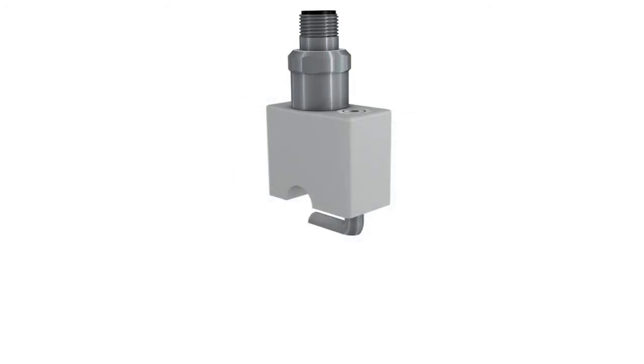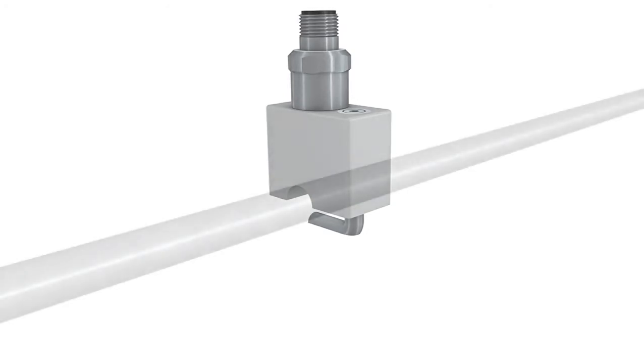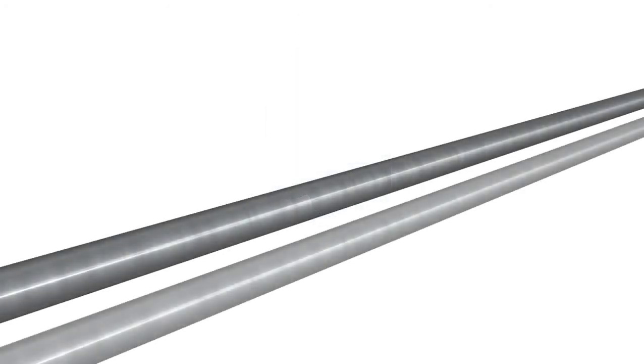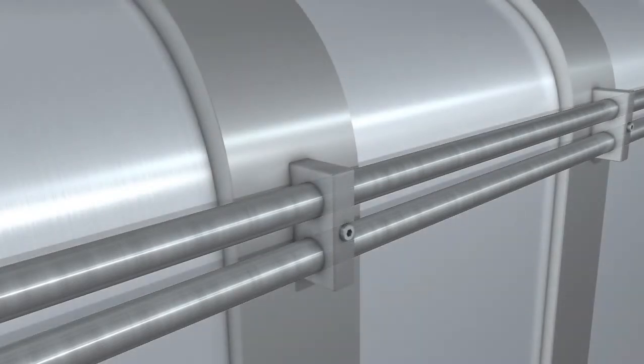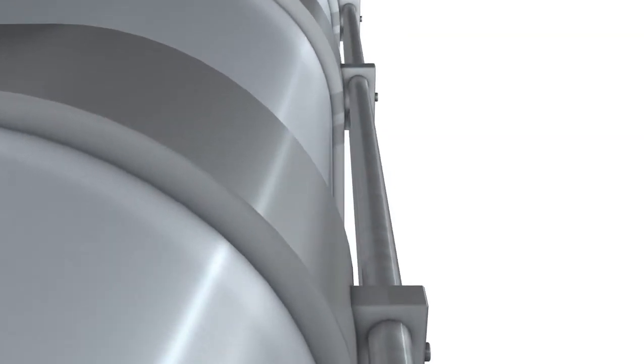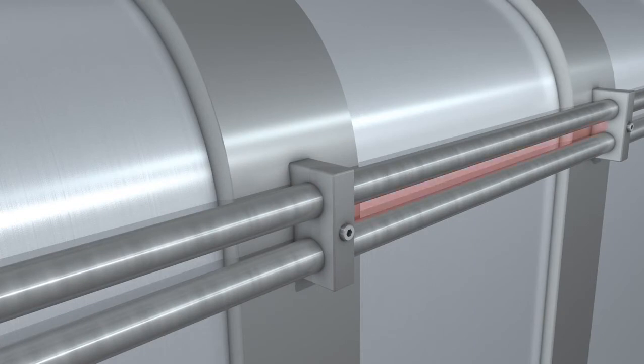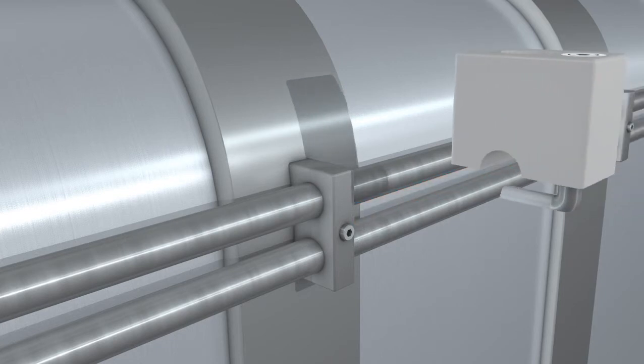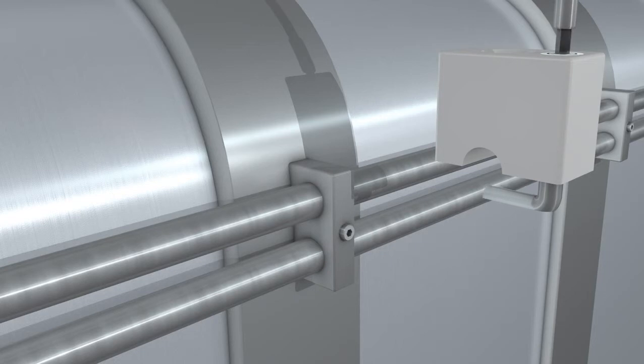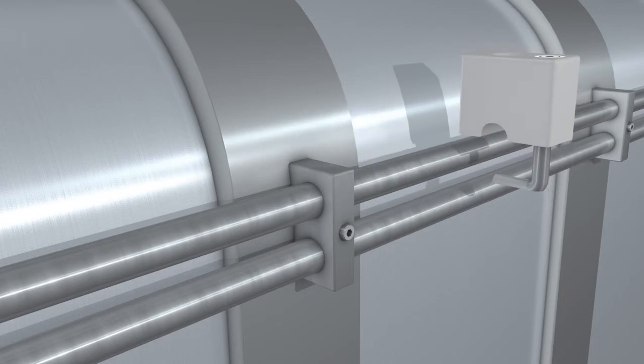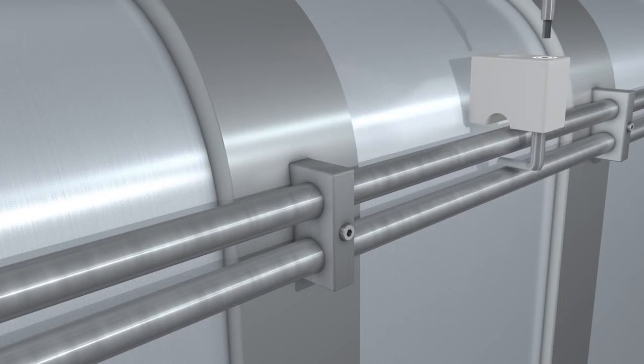A mounting bracket can be used instead of the clamp block to mount devices in tight spaces, for example near walls or close to other pipes. In this example, you can see how the device is mounted between two lines using a mounting bracket. In this case, the bottom part of the clamp block is replaced by a bracket instead of a clamp block. The bracket is loosened to allow the block to be fitted to the pipe. The screw is then re-tightened and the sensor is reattached to the block.